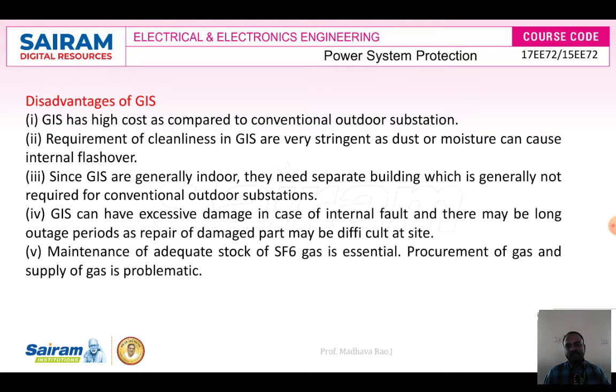But coming to the disadvantages, GIS has a high cost compared to conventional outdoor substations. Since we are using all modernized equipment, the cost of the substation will increase. The requirement of cleanliness in GIS is very strict, as dust or moisture can cause internal flashover. You have to monitor that dust and moisture do not enter the GIS, otherwise it becomes dangerous. Since GIS are generally indoor, they need a separate building, which is generally not required for a conventional outdoor substation. A conventional substation does not need a separate room for installing the air compressor, but here some separate building is required.